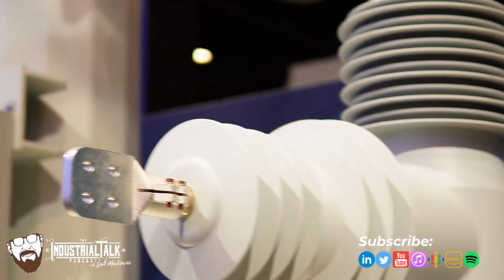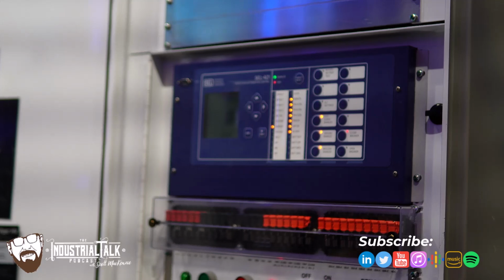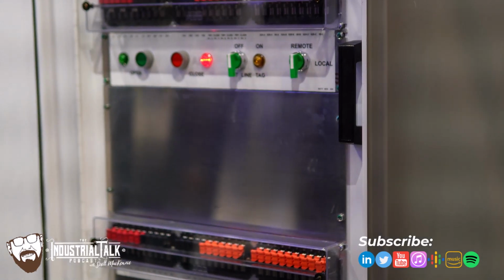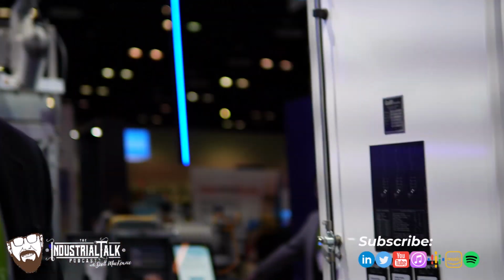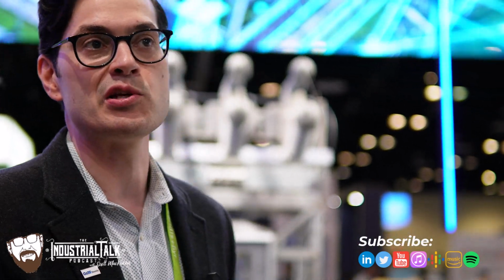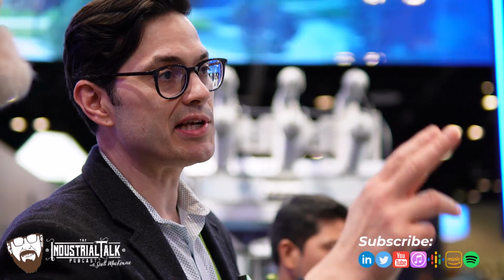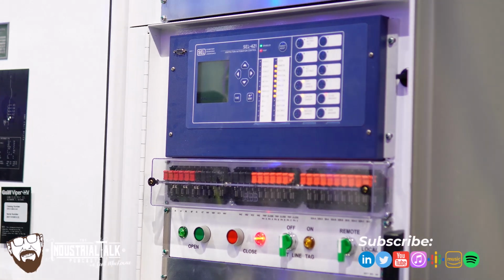And because we've paired this with very popular SEL relays, this is the 421, but we can also do the 651R, and we are looking at pairing it with other relays. This is a device that also can be used in automation schemes if utilities can get comfortable enough with this technology. Remember, it's only been out for a couple of years. Yeah. Can get comfortable with this technology to potentially do some automation schemes at 72 kV. Be the only product in the industry that's capable of doing that. So key features: fault interruption, sectionalizing capability, built-in current and voltage sensing. You can do automation with this. It's paired with commonly available SEL relays for transmission voltages. It's a great product.